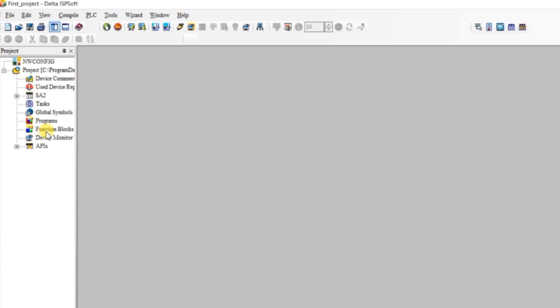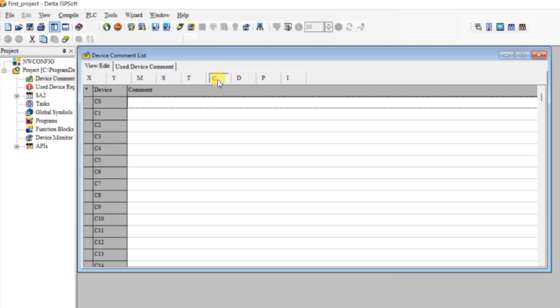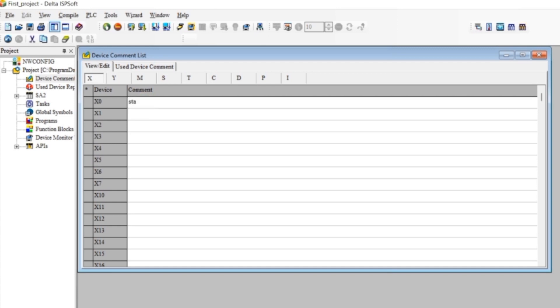After that this box will open showing the location of your file. This is the Device Comment List — double click on it and this box will open. Here we can write comments for our devices. In PLC, X is all our inputs, Y is outputs, M are memory or internal relays, T is timers, C is for counters, and D is data registers. Let me write a comment for X0 — for example I'll write 'start'.